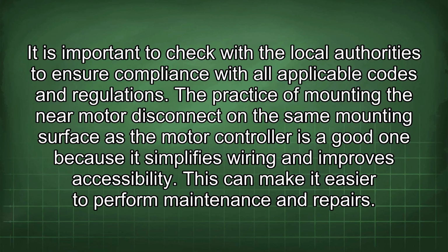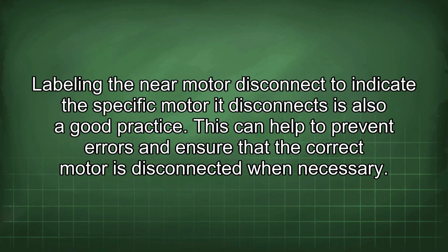The practice of mounting the near-motor disconnect on the same mounting surface as the motor controller is a good one because it simplifies wiring and improves accessibility. This can make it easier to perform maintenance and repairs. Labeling the near-motor disconnect to indicate the specific motor it disconnects is also a good practice. This can help to prevent errors and ensure that the correct motor is disconnected when necessary.